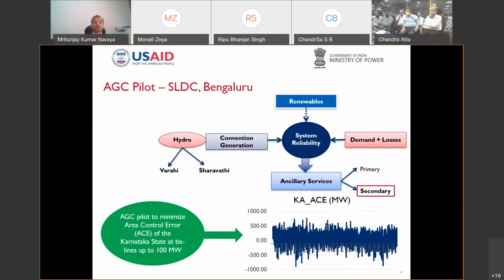The overall idea is to bring down the area control error. The convention used for the ACE signal is that positive means Karnataka is in surplus, negative means Karnataka is in deficit. When the area control error is positive, Karnataka is surplus, and a signal goes to the participating generator - Sharavati at present, and Varahi later - so that the generation comes down.